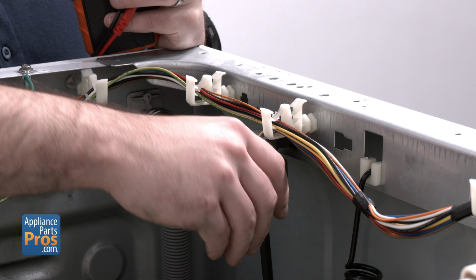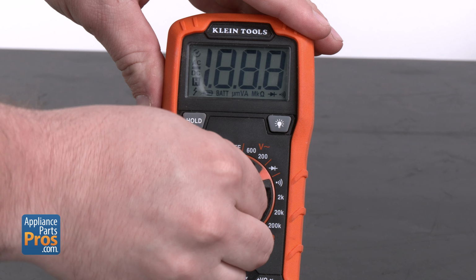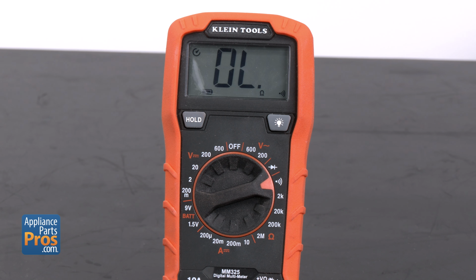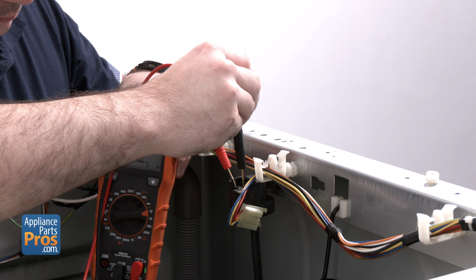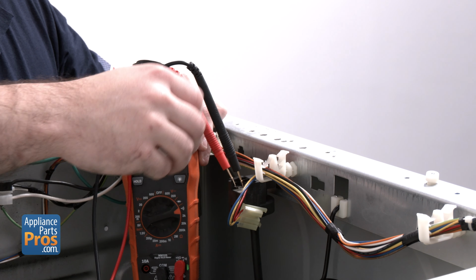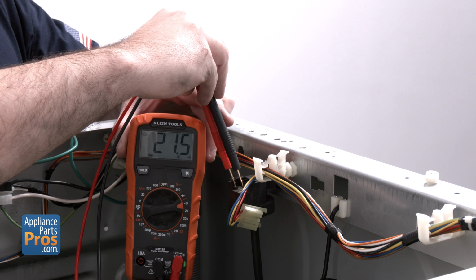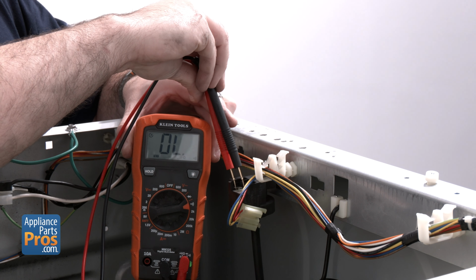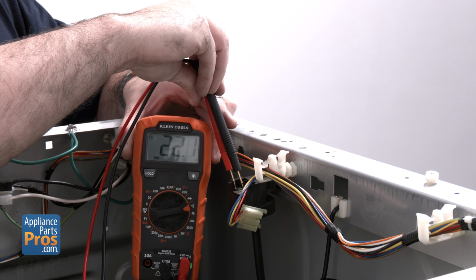Disconnect the wires from the pressure sensor. Set your multimeter to resistance, indicated by the upside down horseshoe symbol. Test the outer two terminals on the pressure sensor. You should see a resistance reading between 21 and 22 ohms. If the resistance is outside of this range, the pressure sensor has failed. If the resistance is within range, continue troubleshooting.